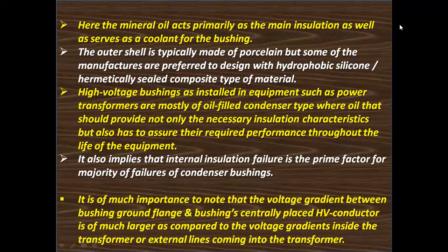It also implies that internal insulation failure is the prime factor for the majority of failures of condenser bushings. It is of much importance to note that the voltage gradient between the bushing ground flange and the bushing's centrally placed HV conductor is much larger compared to the voltage gradients inside the transformer or external lines coming into the transformer.